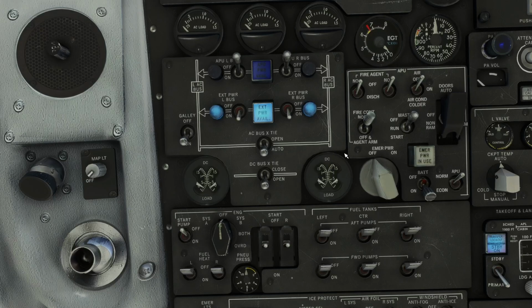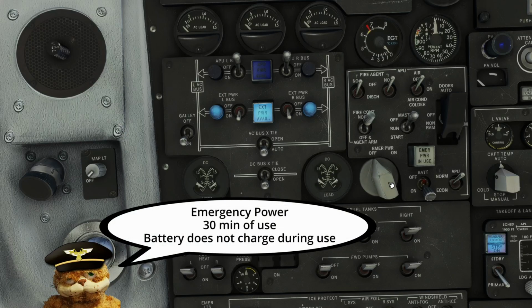Each side has two transformer rectifiers, so you have transformer rectifier 1 and 2 on the left bus and 1 and 2 on the right bus, and that runs the DC system. So if you lose your generator, you lose your DC stuff too, unless you power it off the battery using emergency power, and that's what this big switch is for over here.